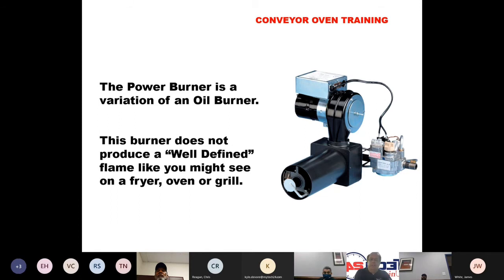This is a power burner. It's a variation of an old oil burner. This burner does not produce a well-defined flame like you might see on a fryer or a grill. This is a big hunk of gas getting blown into a very large opening inside the plenum of an oven. So do not expect to see well-defined flames on large ovens.